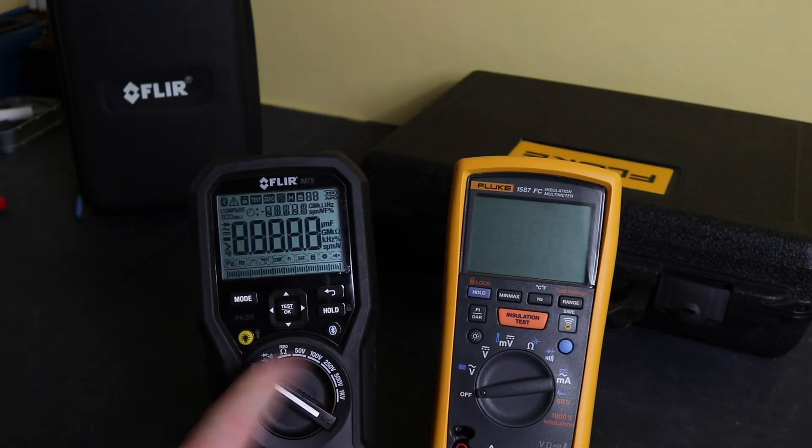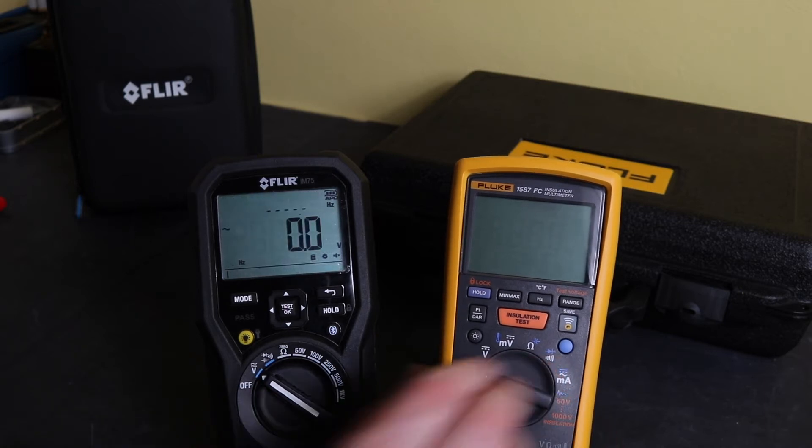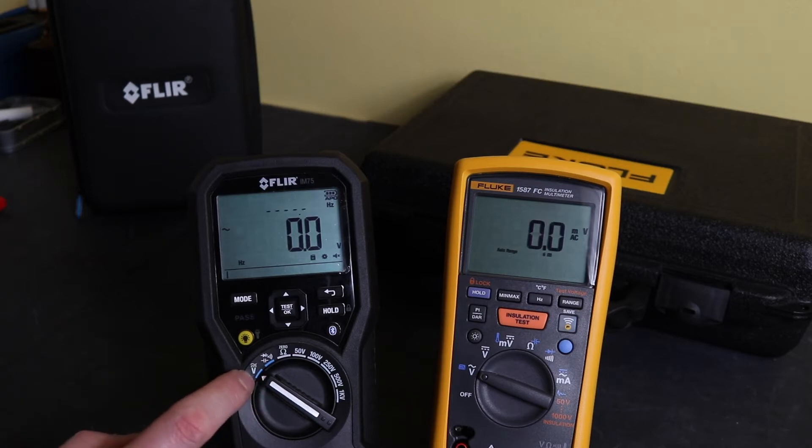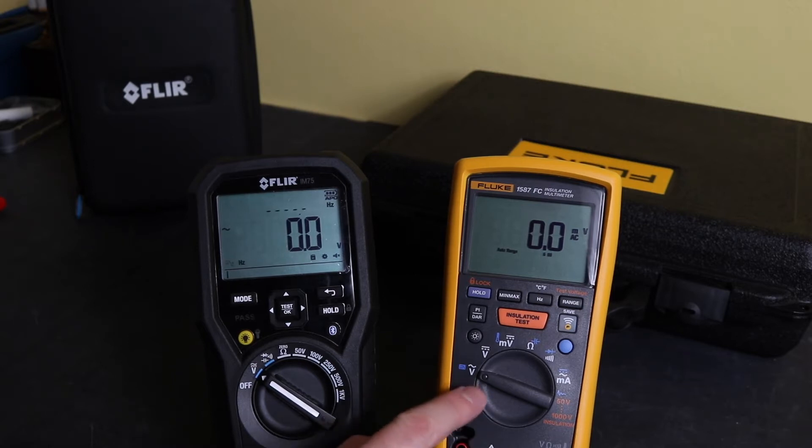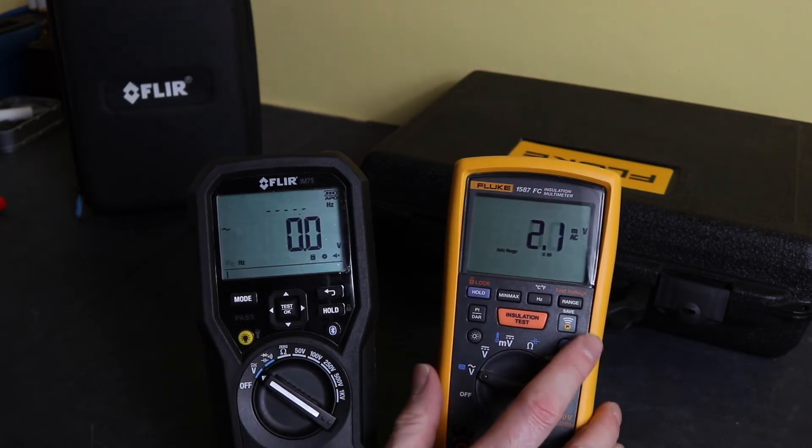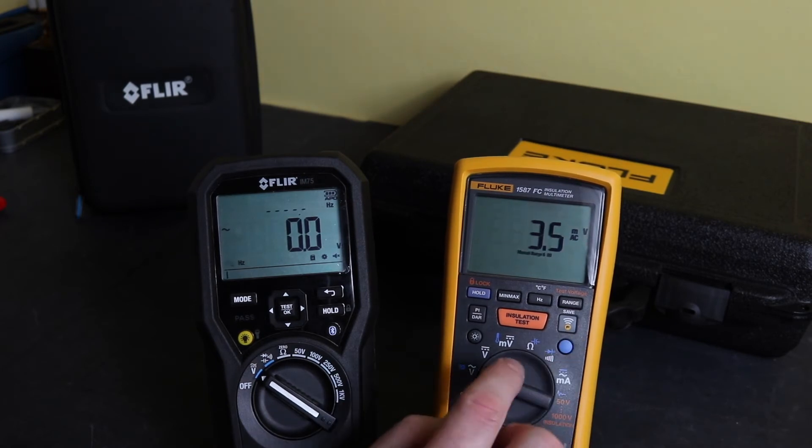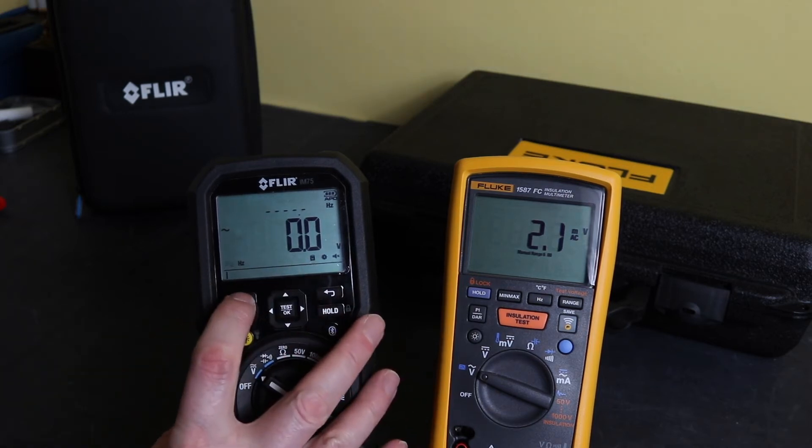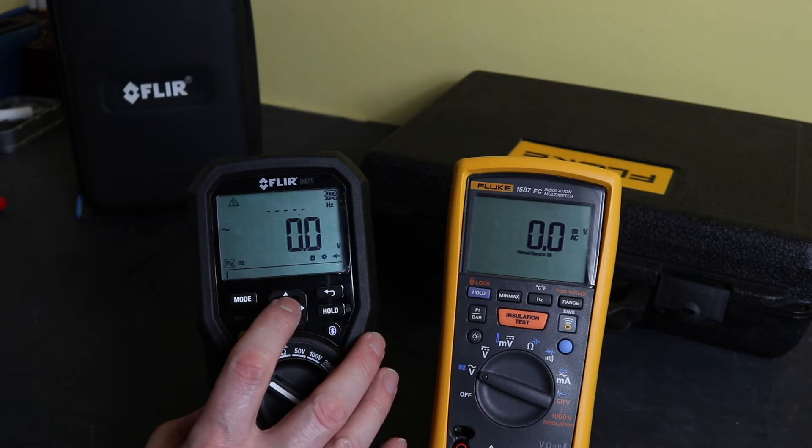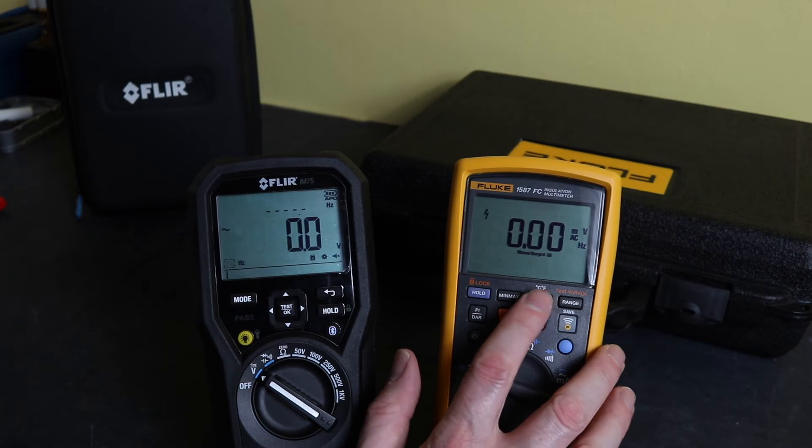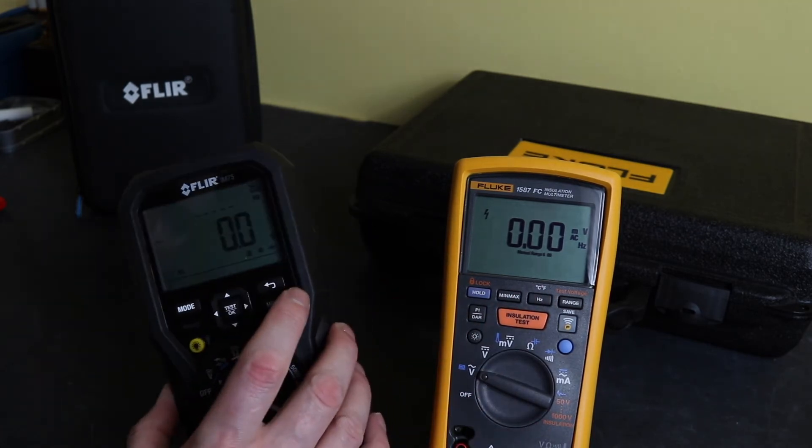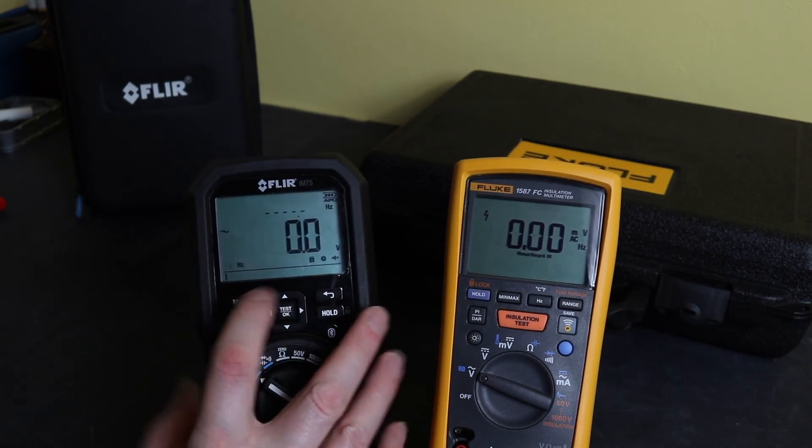Functionality-wise for the instruments, as I said, these are both insulation multimeters. So first setting on the instrument, all selected by the rotary function switch here on both of them. You've got AC/DC volts for the Flir, which is off this jack and the common, and you have AC volts only on this function for the Fluke. You do have a low input impedance option with the option button here on the Fluke that you don't have with the Flir here. But with the Flir you do have a VFD mode that you can utilize and also frequency, which you do have. You can select frequency off the function button at the top there for the Fluke, and you also have a filter mode on this instrument that you don't have on the Fluke.